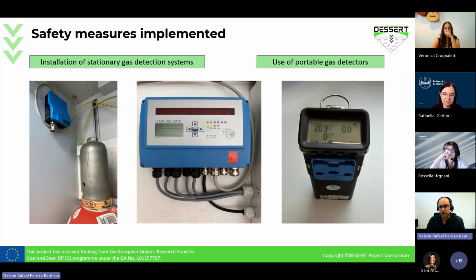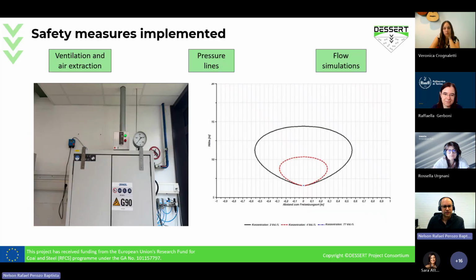We have detectors located at all the single spots where a leak might be possible. Apart from that, our technicians also use portable gas detectors, in case they need to go into the rooms where the tests are taking place. Each of the cabinets, for example this one here, either bottle cabinets or where leak detectors and other equipment are found, also have ventilation and air extraction, as well as all high pressure lines coming with an exhaust to the atmosphere, outside the building.